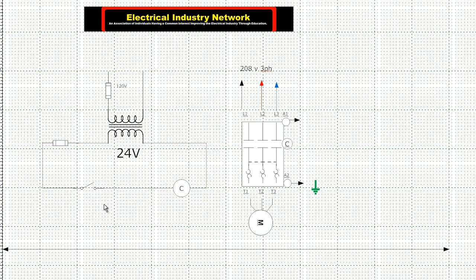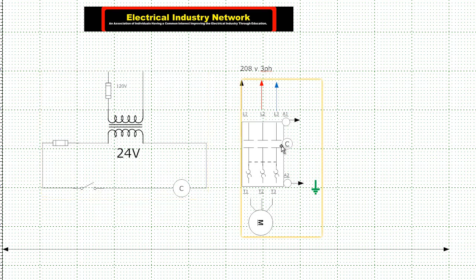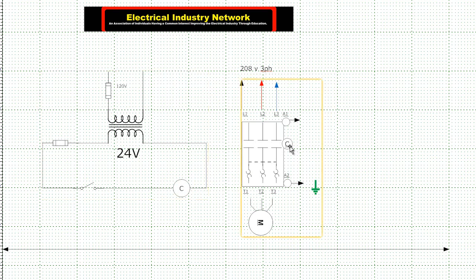So when the operator was standing back at the pedestal and basically closed that switch, what it did was it sent power to the coil. These two are energizing that coil. It sent that power out, and we had our 24 volts between A1 and A2.